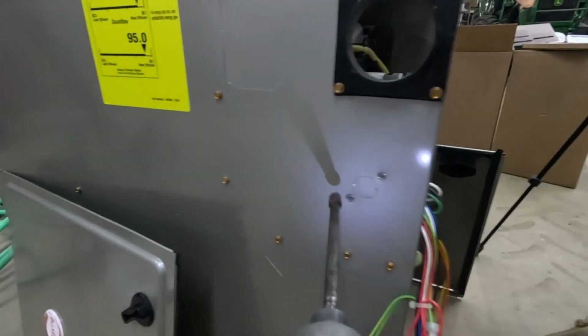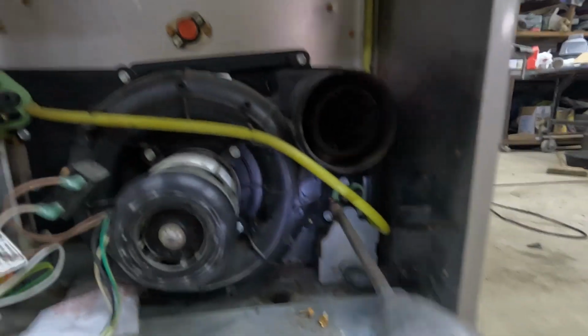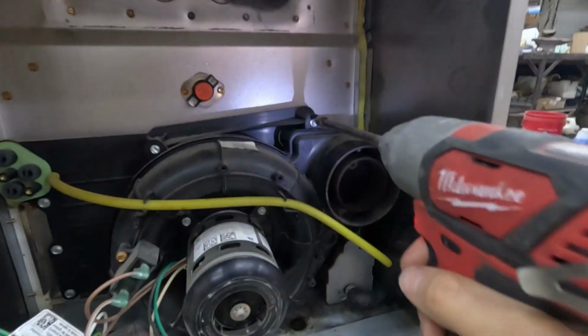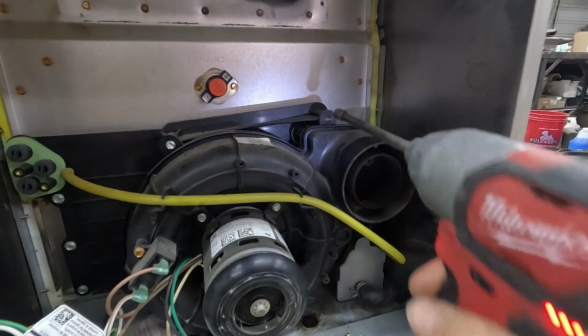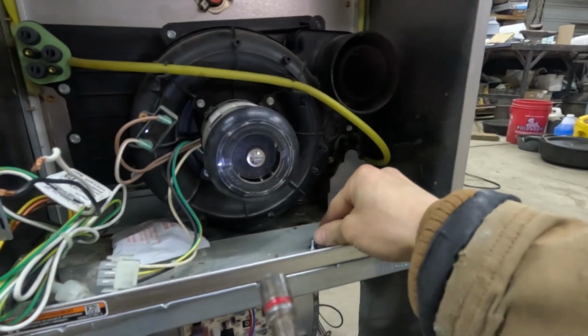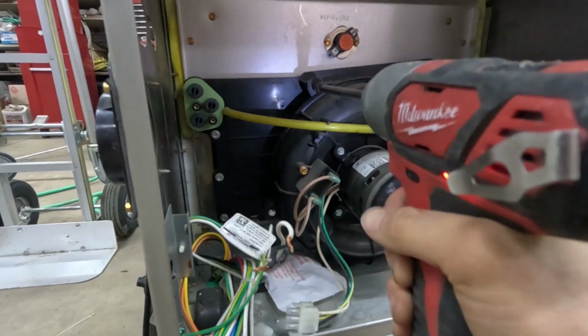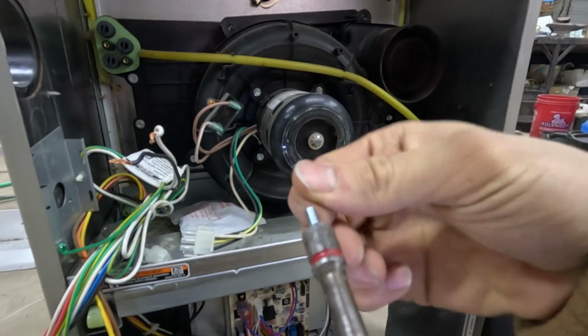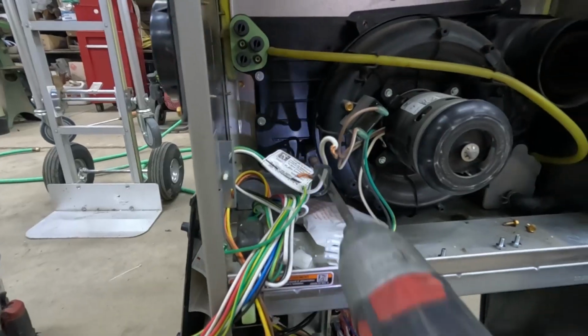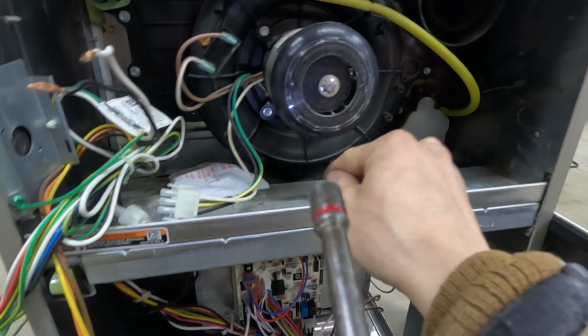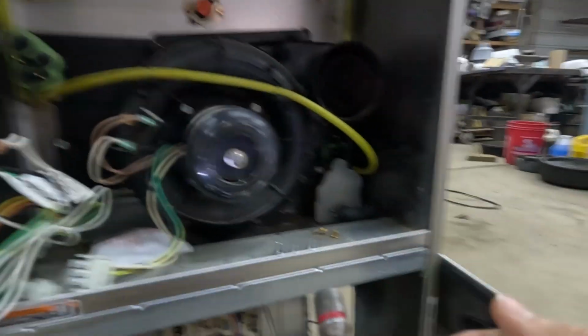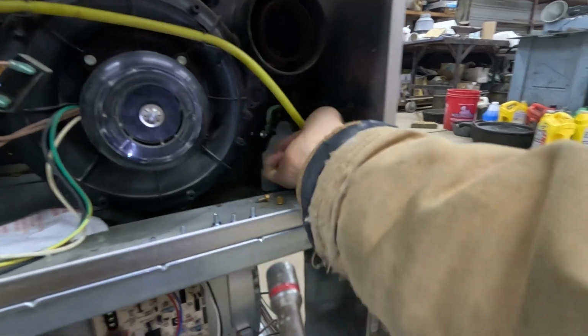Now I can remove the combustion blower. Now these are a fine thread screw, so you got to keep them separate. When you put them back in, don't use the impact because you don't want to cross thread them. See how they're kind of finer. And we'll just leave this piece of tubing on the combustion blower.